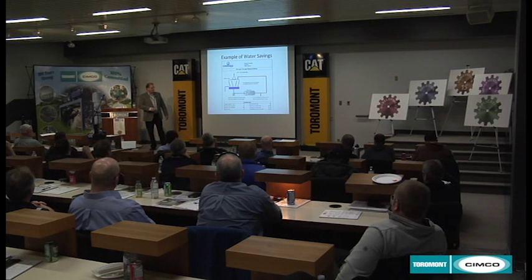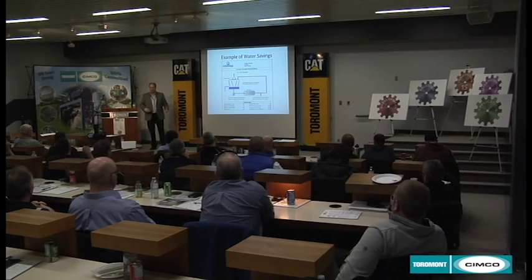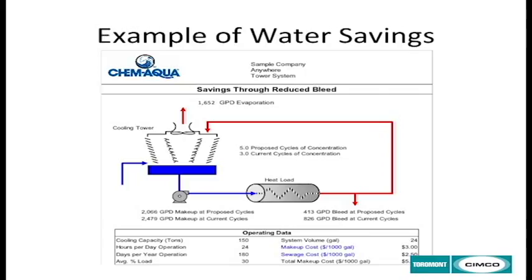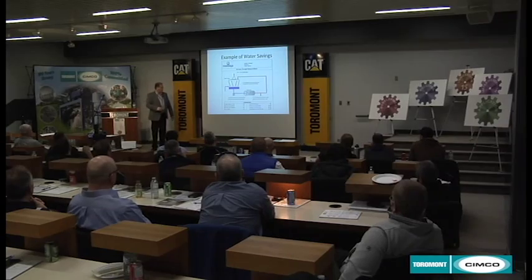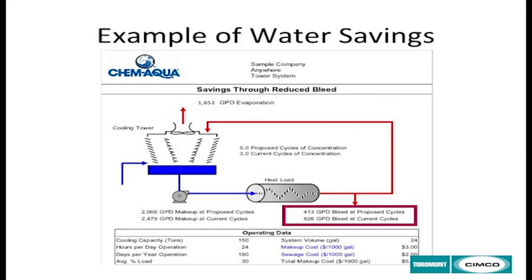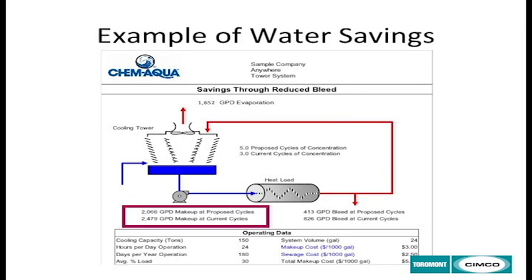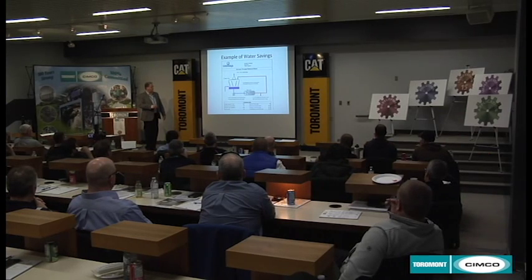I took an example of a 150-ton cooling tower running 24 hours a day, 180 days of the year at 30% load capacity, so 30% evaporation. I use basically $3 per 1,000 gallons of makeup water, and $2.50, or that comes to about $1.50 a cubic meter, which is kind of a common denominator that I found in the industry that people pay for. If I were to take my current cycles, how many gallons of bleed I do, versus my proposed cycles, which is taking it from 3 cycles of concentration, that's how many times I leave the water in a tower before I bleed it. If I go from 3 to 5, you can see I could save up to 400 gallons per day of makeup in the tower. 400 gallons per day. So if you're not concerned with cost, consider the amount of water you're wasting. That's the water savings we're talking about.